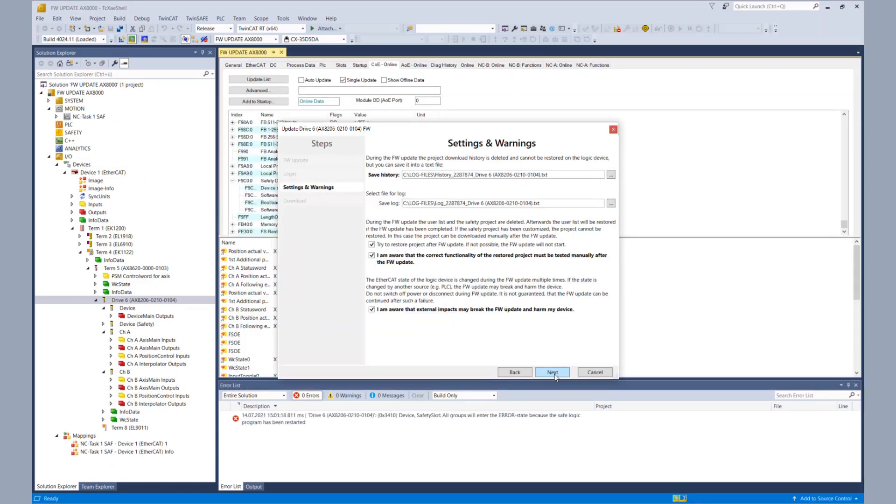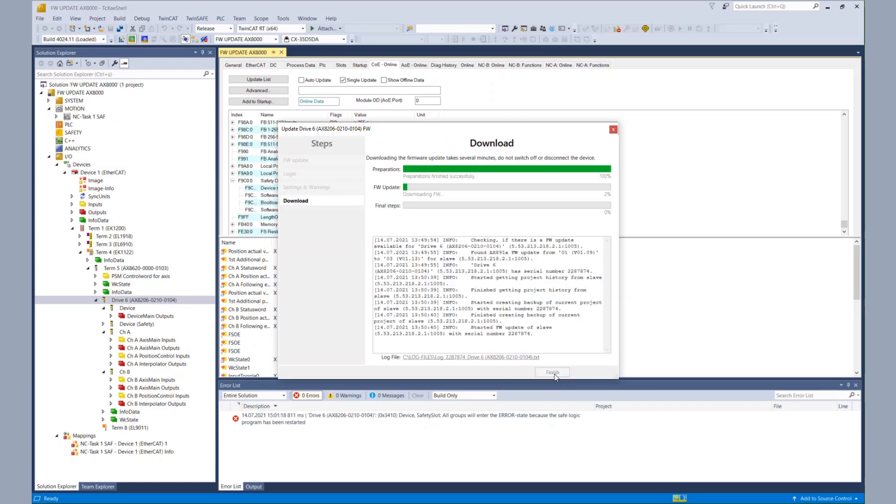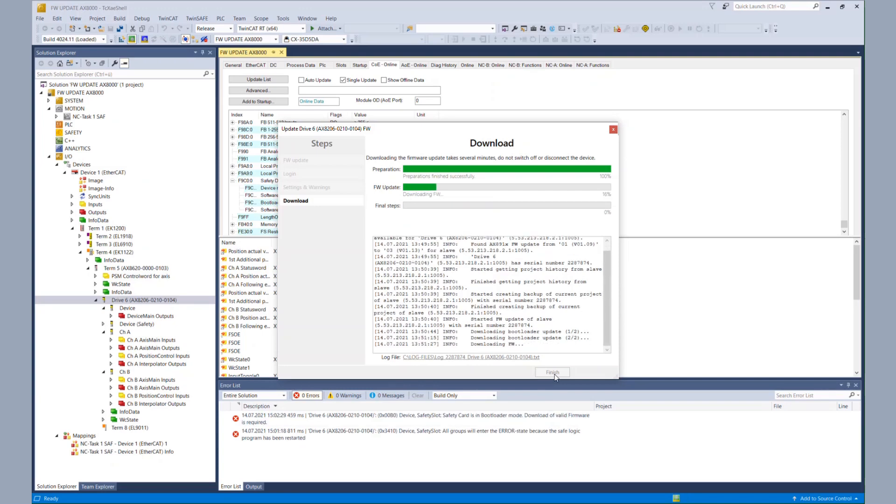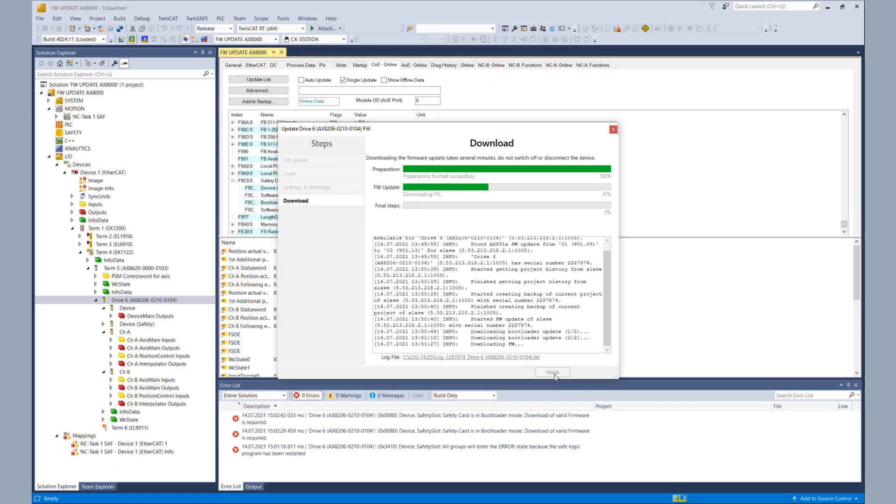So now we can start the actual update. For your information, this video is recorded with increased speed. So in real time, it takes more time than shown here. At the beginning, the project history is saved to hard disk and we do a backup of the safety project from the AX8000. The bootloader is updated to the current version. And last but not least, the firmware is updated.